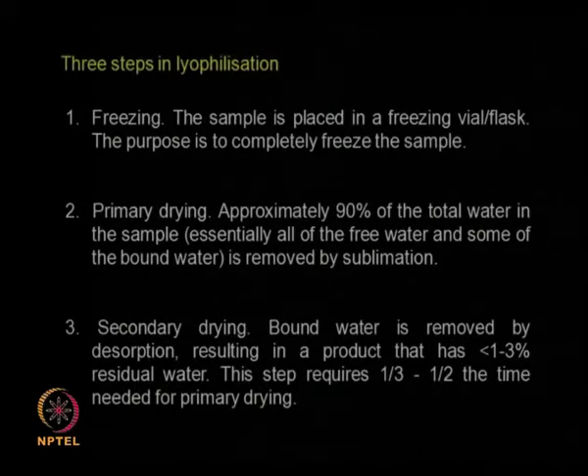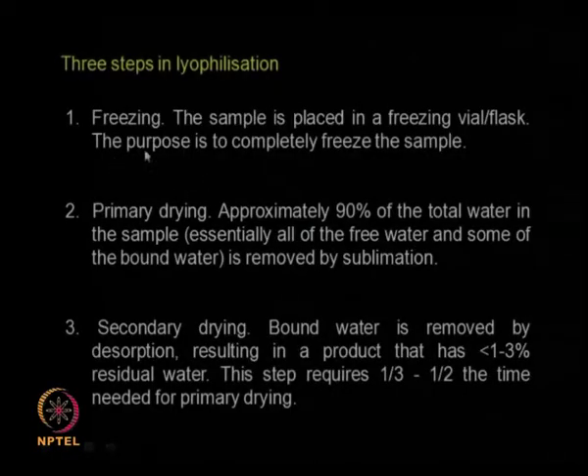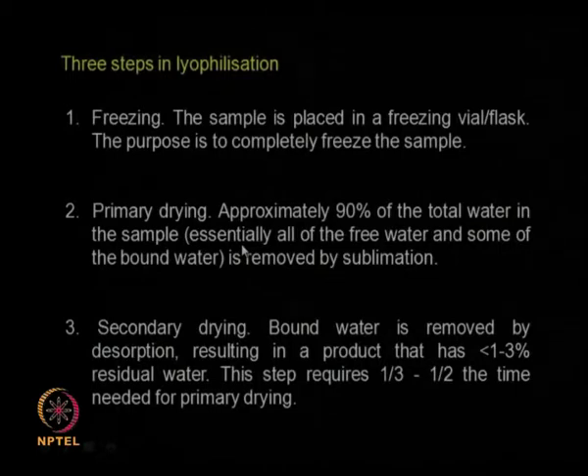The three steps in lyophilization: first, freezing — the sample is placed in a freezing vial or flask. In a laboratory you take the material in a flask; in pharmaceutical industry you take it in a vial because it becomes easier to completely seal it after freeze drying. Next, by sublimation you remove the solid ice into vapor — about 90 percent of the total water in the sample goes away.